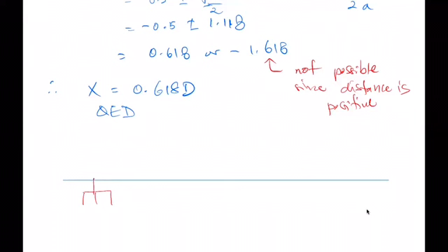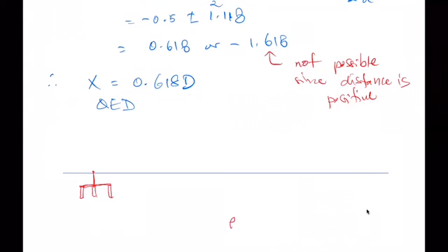Maybe you have 3 rods there, and you want to measure the resistance of this electrode having a soil resistivity rho. So all you need to do is bring 3 probes.